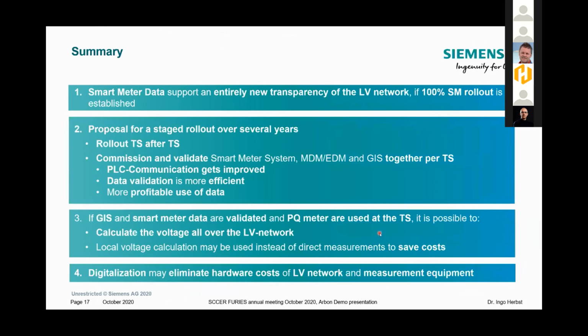So what's the summary? Smart meter data really gives you new transparency of the low voltage network if you have 100% smart meter rollout, which we had in this case. With our new strategy in Switzerland, we should have that in a lot of DSOs within the next years. Now, the proposal for a staged rollout over several years is that you roll out transformer station by transformer station up to 100%, because if you have a PLC system, at least your communication gets heavily improved.